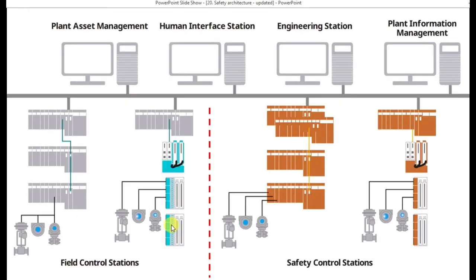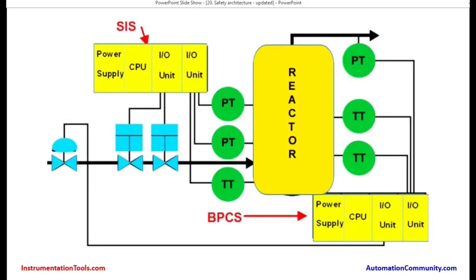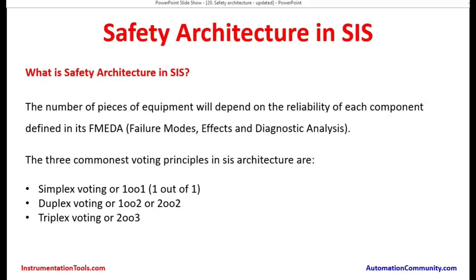For example, if it is a one-out-of-two arrangement, two sensors are used. In a one-out-of-two combination, either one showing higher pressure can give a signal for the safety system controller to work. This is known as a voting technology. Sometimes it may be three sensors, out of which two going high can cause a safe shutdown.